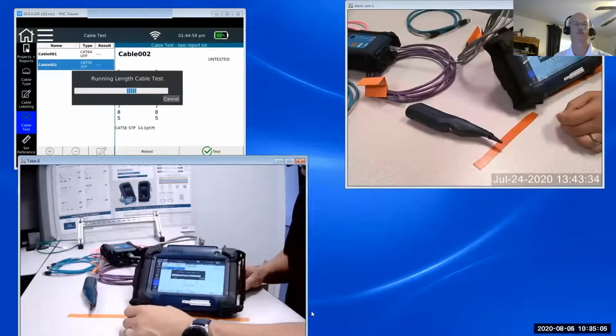First thing it's going to do is run a wire map test, confirming that all 8 conductors are wired as they should be, as well as the shield, since we've set that test up to look for a shielded cable. It's then going to look at signal to noise ratio, the delay, and finally run a bit error rate test.